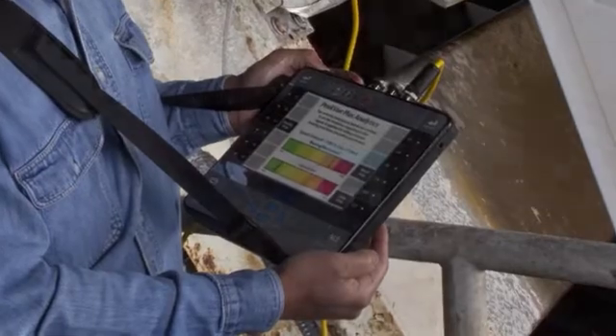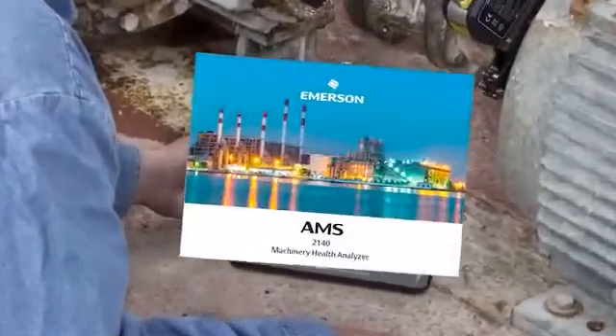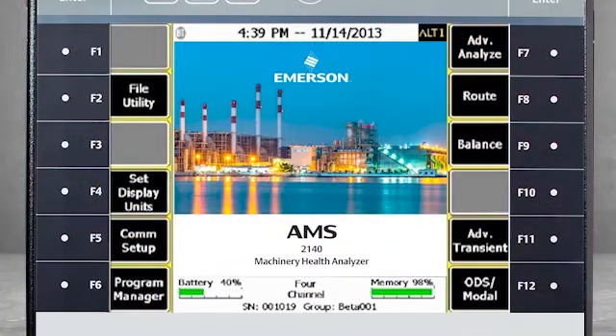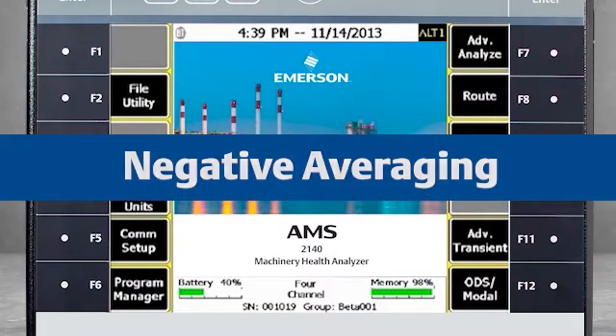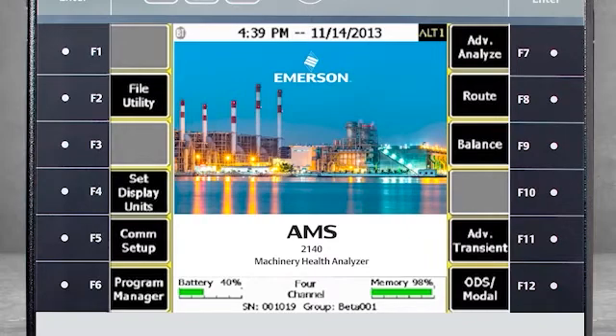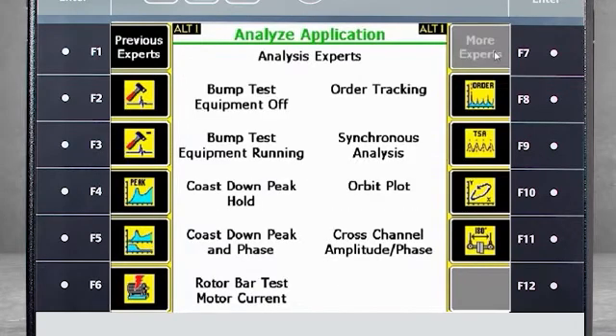As we review this technique, you'll note a visual reference to the CSI 2140. Please be aware that this product has been rebranded as AMS. I am going to show you how to collect data to determine the natural frequency of a machine that is not currently running — this is called negative averaging, or sometimes a bump test. Here you see the home screen of the AMS 2140. Select F7 Advanced Analyze, then F7 for more experts, and then select F2 Bump Test Equipment Off.